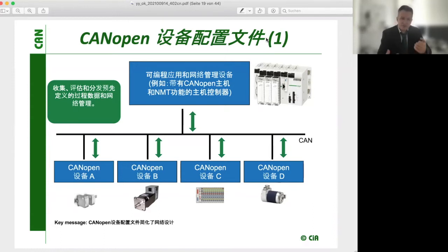So by default, there are already some settings for communication of process values around the network. So position and control information, status of the drive, target position, such things actually have to be configured and transmitted over the network to the network component, network node, which takes this information, or the kind of trajectory generator or motor, which sets everything in motion based on the data received from the bus. So this is a device profile.